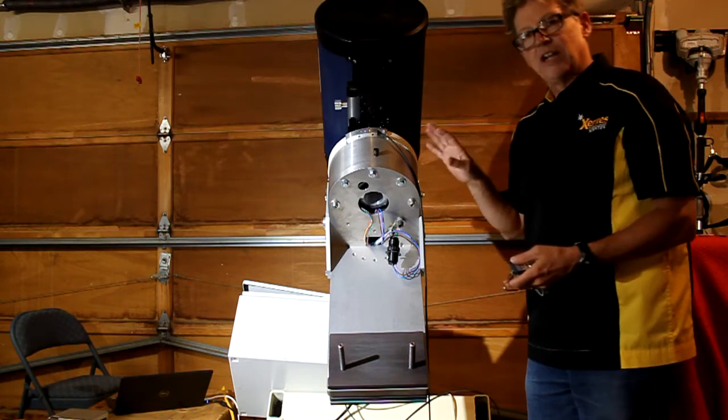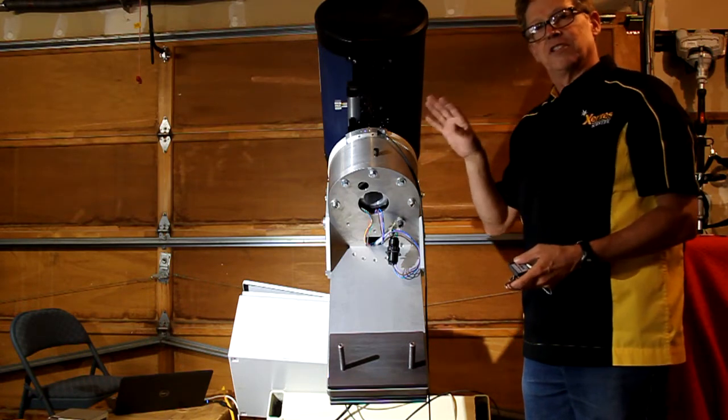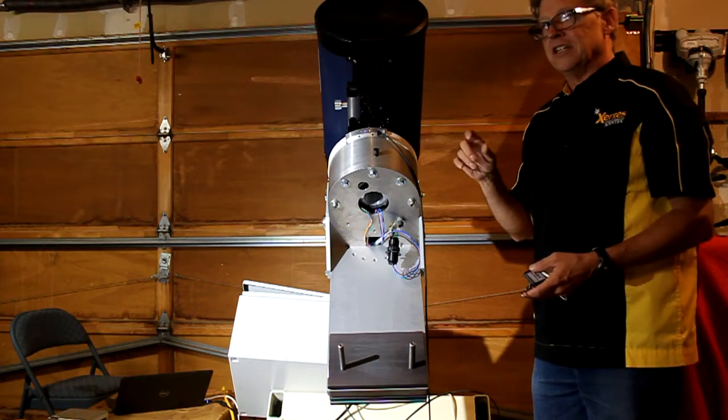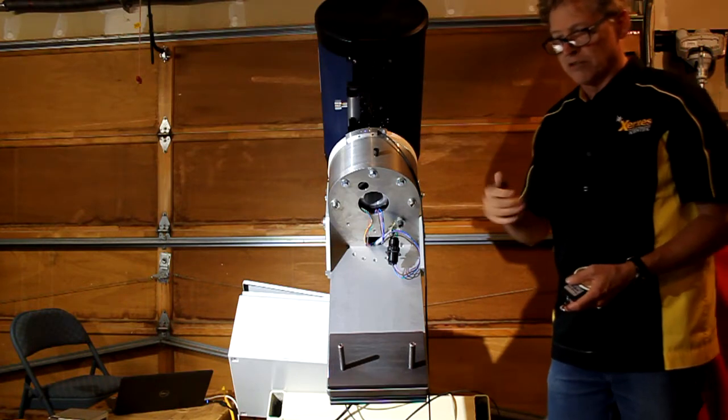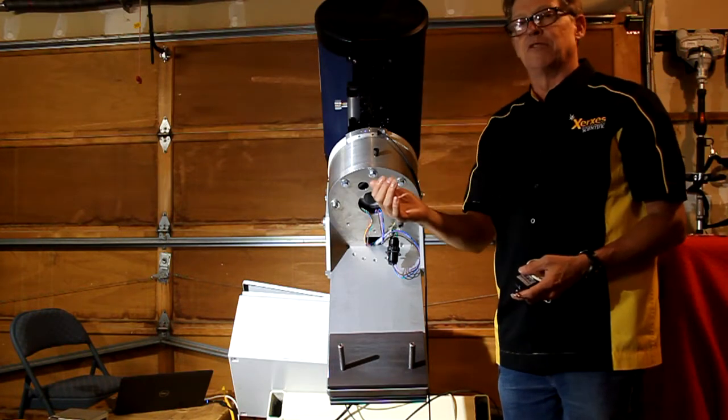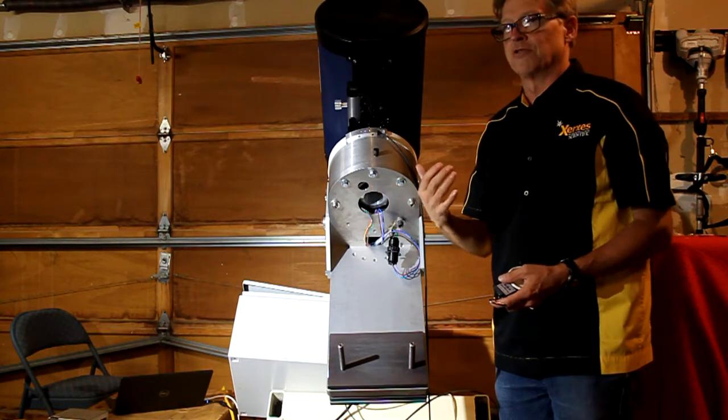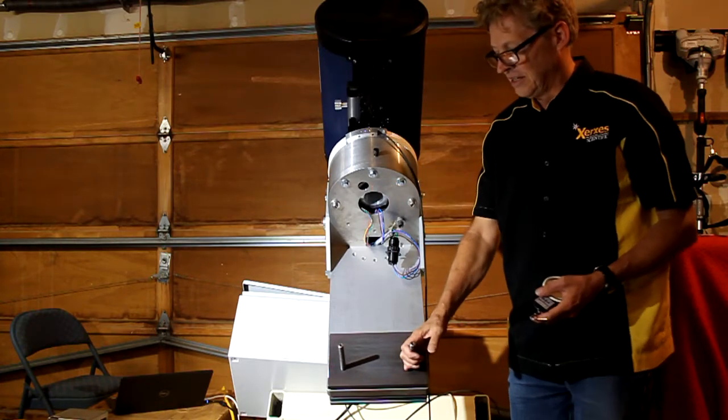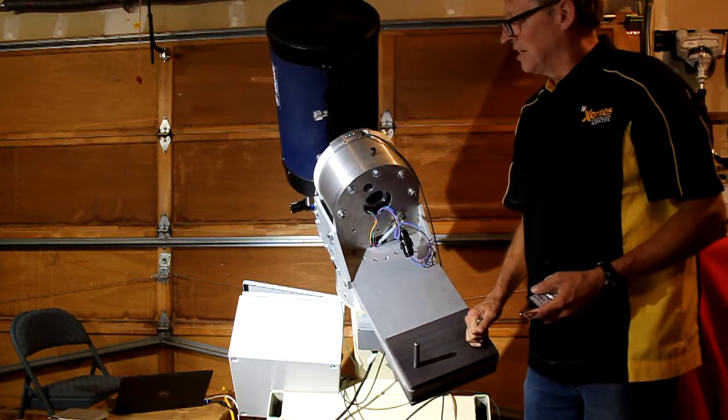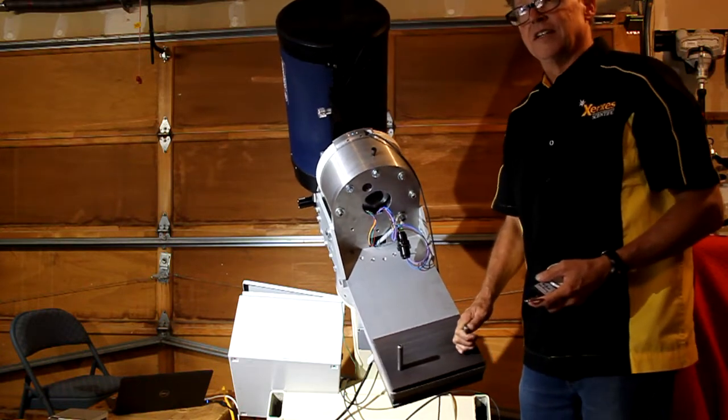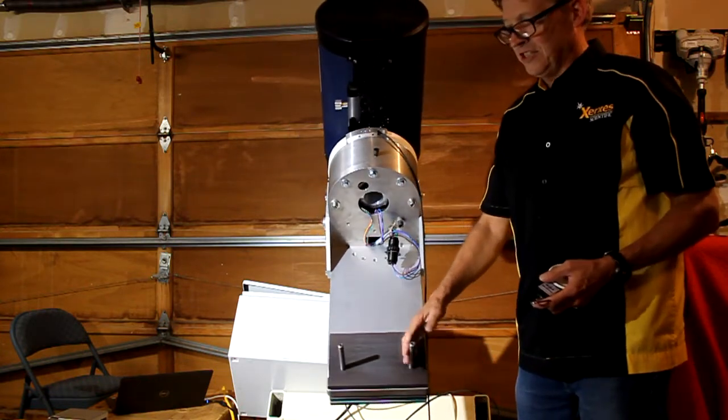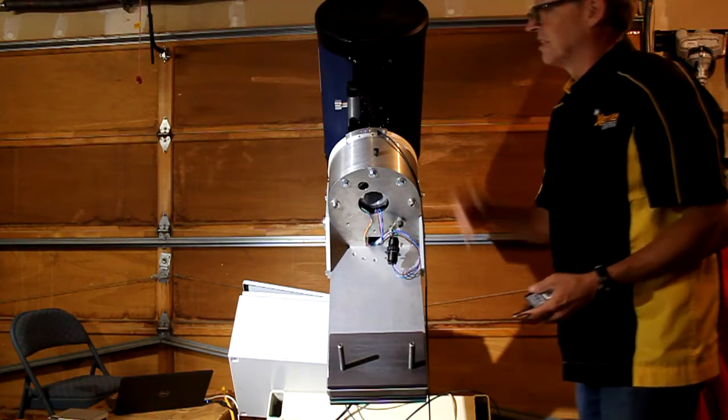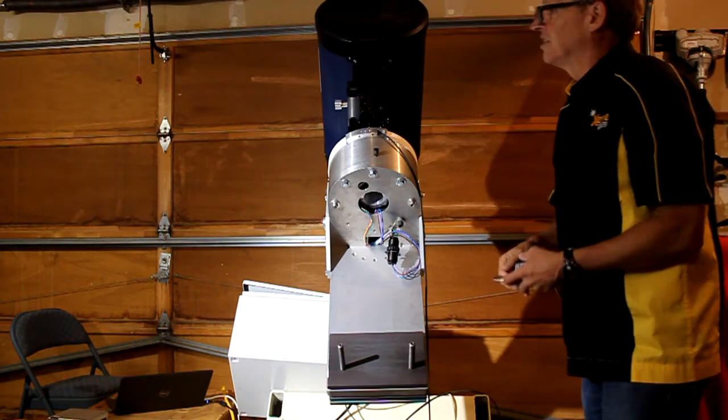And before a breakaway point, the servo loop is still in control. It's fully closed. Once you pass breakaway torque, you hit the torque limit and the torque limiter is turned on and the control loop now is torque limited. It's not going to be position limited, but I can sit here and I can hold it and it'll push against me. I can feel it and then I release it and it'll come back into control to the commanded position and velocity.